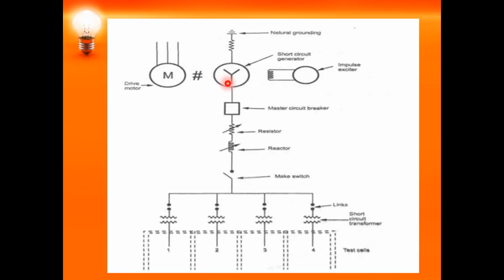The design of this type of short circuit generator is different from your normal generator. These generators are designed to have a very low reactance, so that it gives the maximum short circuit output. They are provided with a flywheel, to supply the kinetic energy during short circuits. You can see here this generator is being driven by a 3-phase induction motor. The short circuit current will have a demagnetizing effect on the field of the generator. Due to this, the field current will be low, so the generator EMF will also be low.